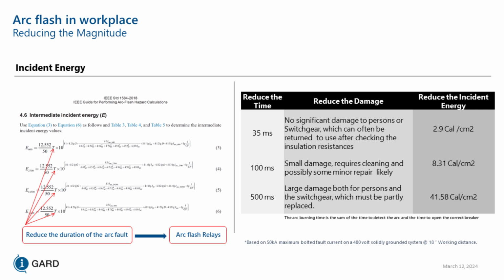But they only protect a minor area of your zone. Differential protection only protects a piece of equipment. Arc flash relays only protect a piece of equipment. High resistance grounded system protects your entire system, all of the return current that's coming in. It limits the fault current.